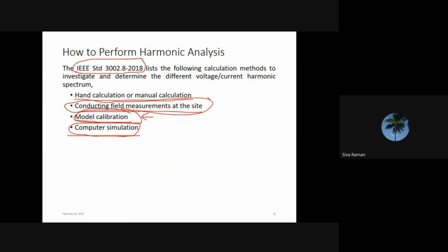In most cases, computer simulation is the method widely used because it does not involve any practical elements. For example, if you need to do the field measurement at site, the site should be in operation, then only we can do it. But when the plant is in the planning and design stage, and you are the developer going to develop a 250 megawatt solar plant in some location in India, when you have some development planning in your mind, at that time computer simulation is the best method to perform the harmonic analysis. So the main advantage is that it does not involve any practical elements.